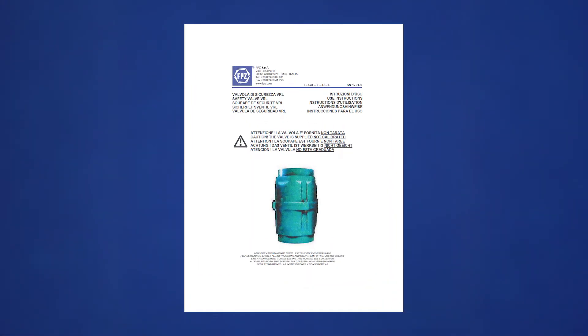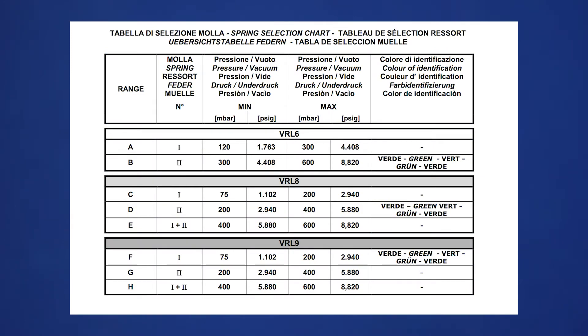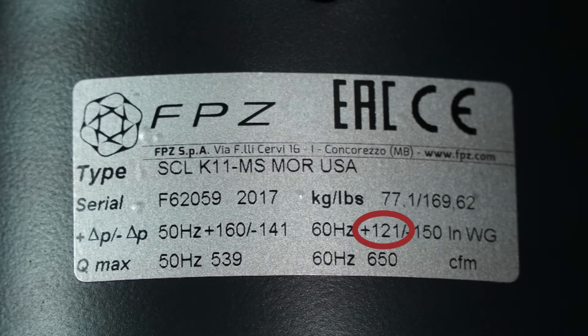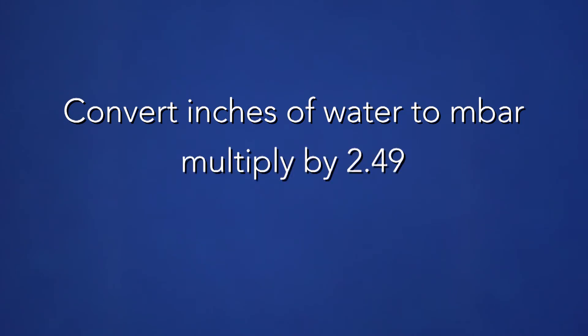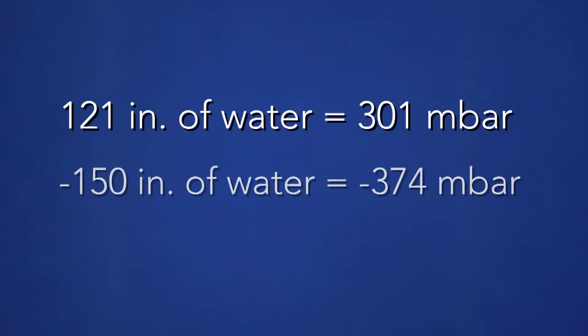To determine the correct spring, refer to the safety valve operating instructions. The safety valve chart will list the pressure range for each spring combination. In our example, we are using the VRL-8 3-inch safety valve. The silver spring has a minimum set point of 75 millibar or 1.1 PSI and a maximum set point of 200 millibar or 2.9 PSI. The green spring has a minimum set point of 200 millibar or 2.9 PSI and a maximum set point of 400 millibar or 5.8 PSI. For pressure above 5.8 PSI, both springs are used. In our case, the set points are 121 inches of water for pressure or negative 150 inches of water for vacuum. We will convert inches of water to millibar by multiplying by 2.49 so we can use the spring selection chart. 121 inches of water is equal to 301 millibar and 150 inches of water is equal to 374 millibar, so we will use the green spring.